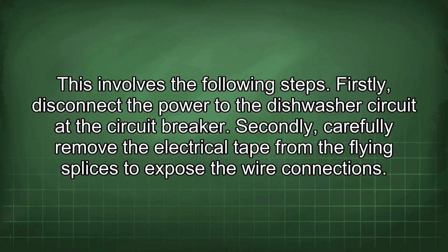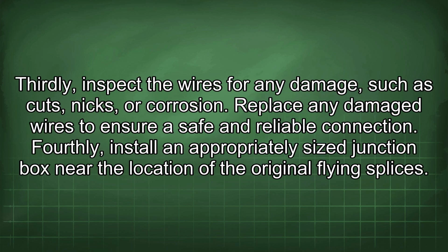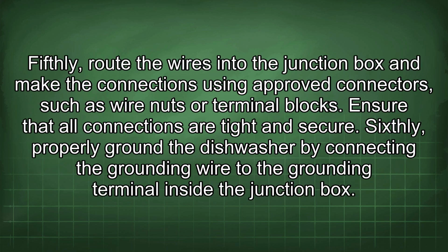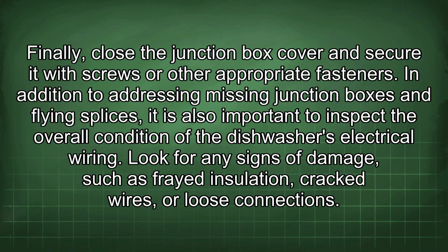This involves the following steps. Firstly, disconnect the power to the dishwasher circuit at the circuit breaker. Secondly, carefully remove the electrical tape from the flying splices to expose the wire connections. Thirdly, inspect the wires for any damage, such as cuts, nicks, or corrosion. Replace any damaged wires to ensure a safe and reliable connection. Fourthly, install an appropriately sized junction box near the location of the original flying splices. Fifthly, route the wires into the junction box and make the connections using approved connectors, such as wire nuts or terminal blocks. Ensure that all connections are tight and secure. Sixthly, properly ground the dishwasher by connecting the grounding wire to the grounding terminal inside the junction box. Finally, close the junction box cover and secure it with screws or other appropriate fasteners.